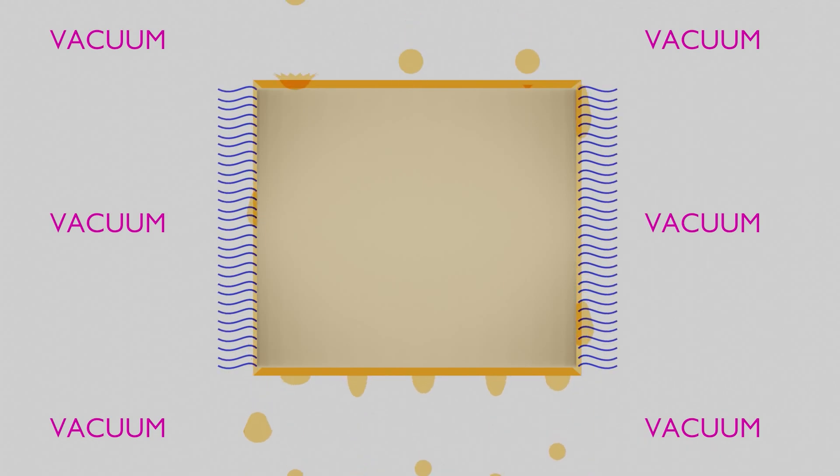And it's this combination of high porous packed bed surface area, a warm thin film of constant flowing oil, and low air pressure created by the vacuum in the vacuum tower, which creates the perfect environment for rapid water evaporation and dehydration out of the oil.